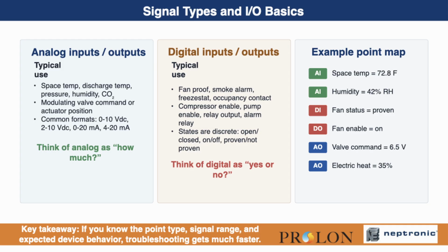In a constant volume packaged cooling-only unit serving an office, the space temperature sensor is typically an analog input because the controller is reading a changing temperature value. The fan status proof is typically a digital input because it is either proven or not proven. The fan enable relay is typically a digital output because the controller is commanding the fan on or off. If the unit has an economizer damper with a modulating actuator, the damper command is typically an analog output because the controller may send a varying signal such as 0 to 10 volts.